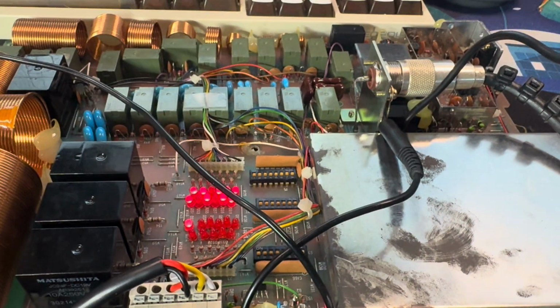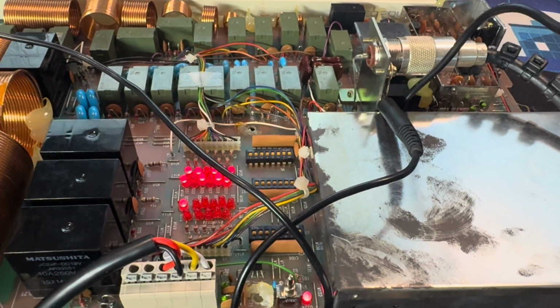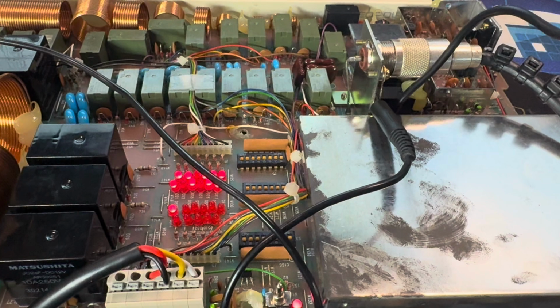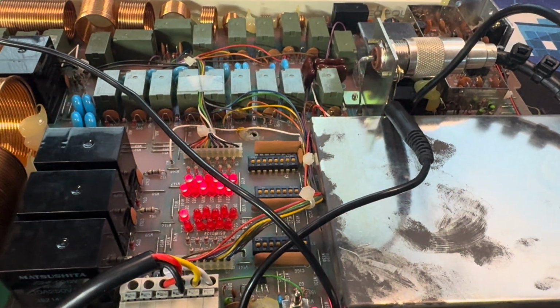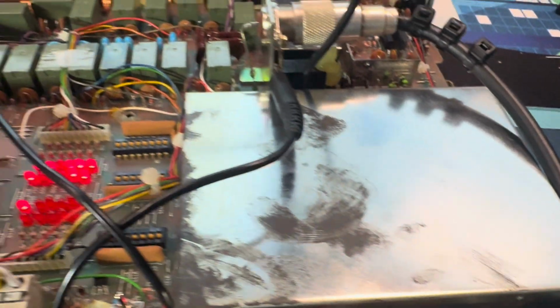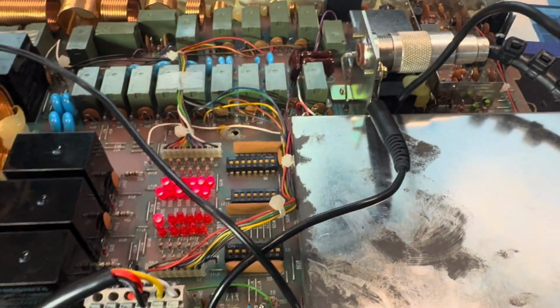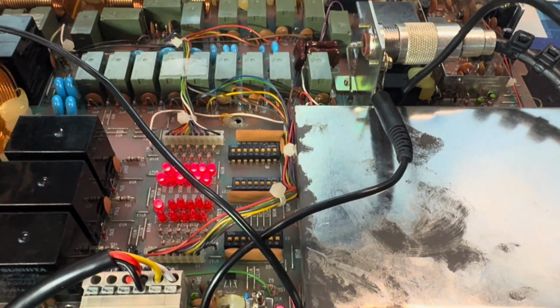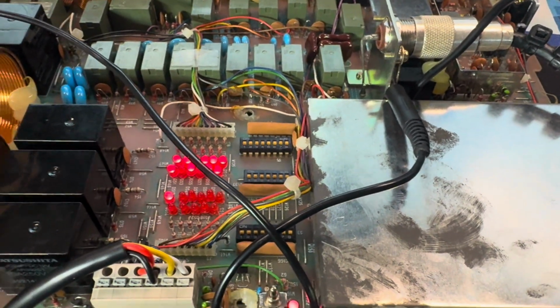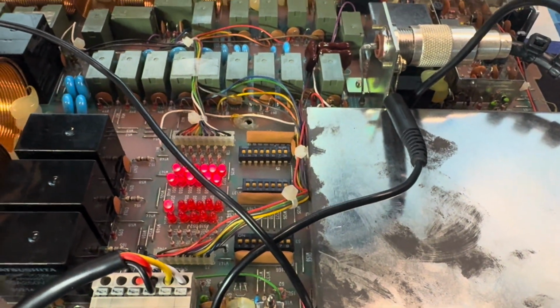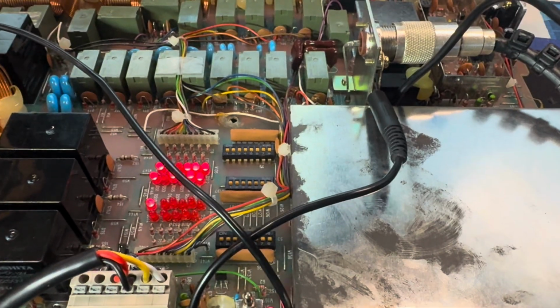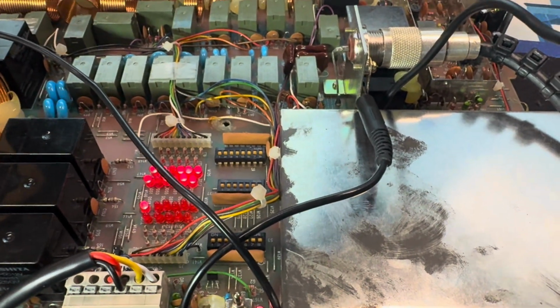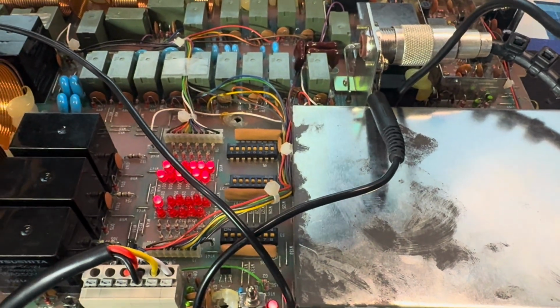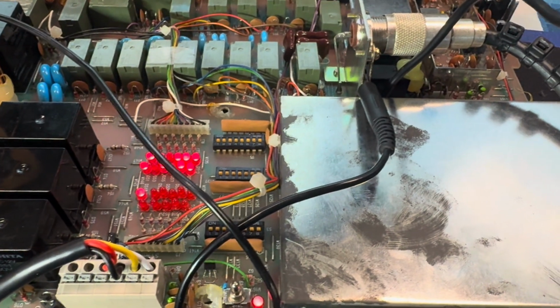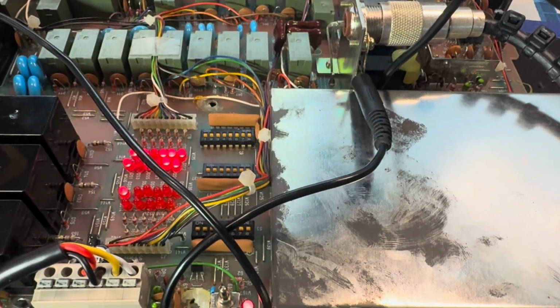Here we go, the guts of the Icom AT-130. So I wired this up last night. It would not work, it would not tune. I looked inside the CPU compartment here. There was a supercapacitor that this uses for memory backup, and knowing what I know of Icoms, they wire that in parallel with the VCC for the CPU, and when those capacitors or little batteries fail short, the CPU cannot come out of reset. So I desoldered that, and it started tuning, but it couldn't find a match.